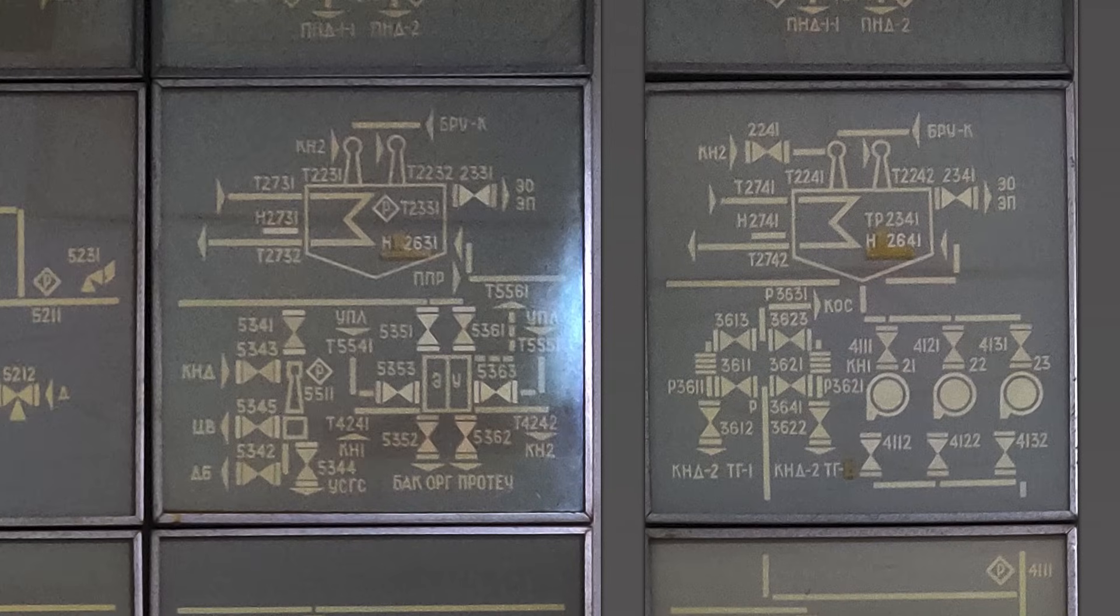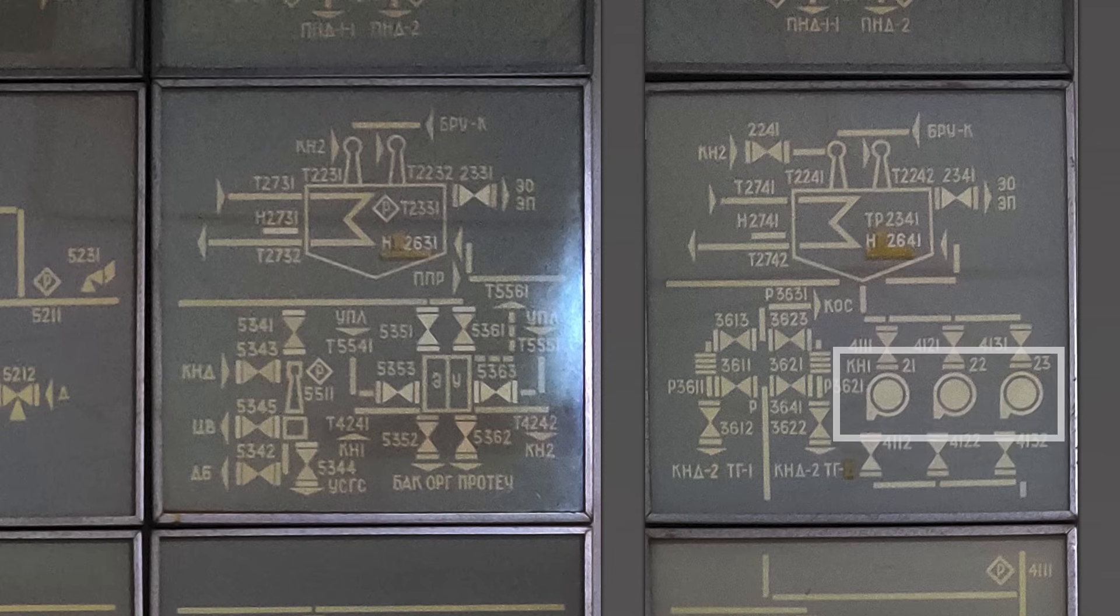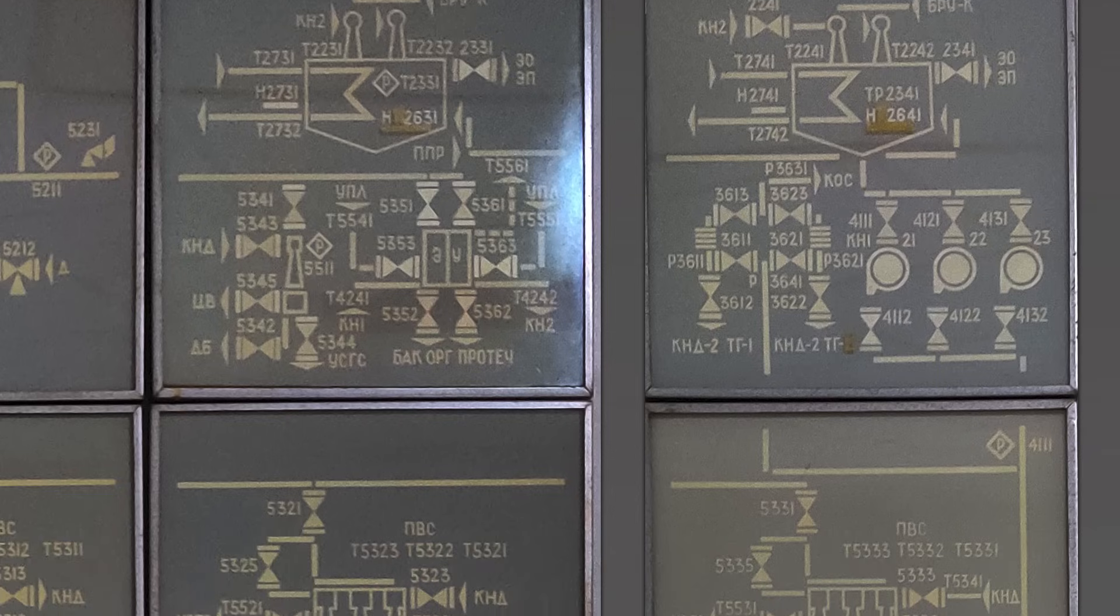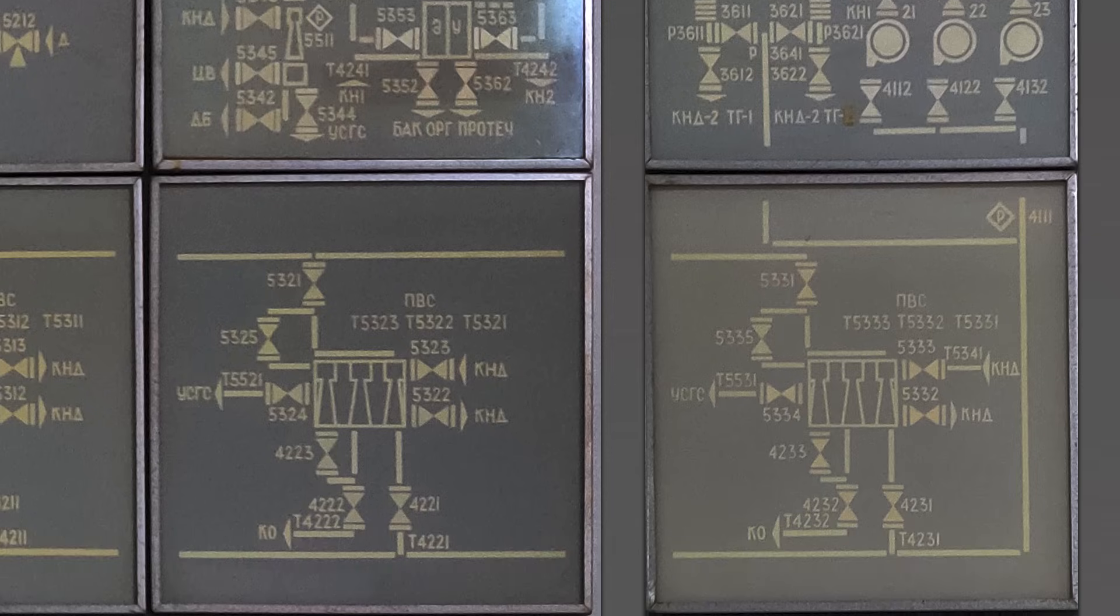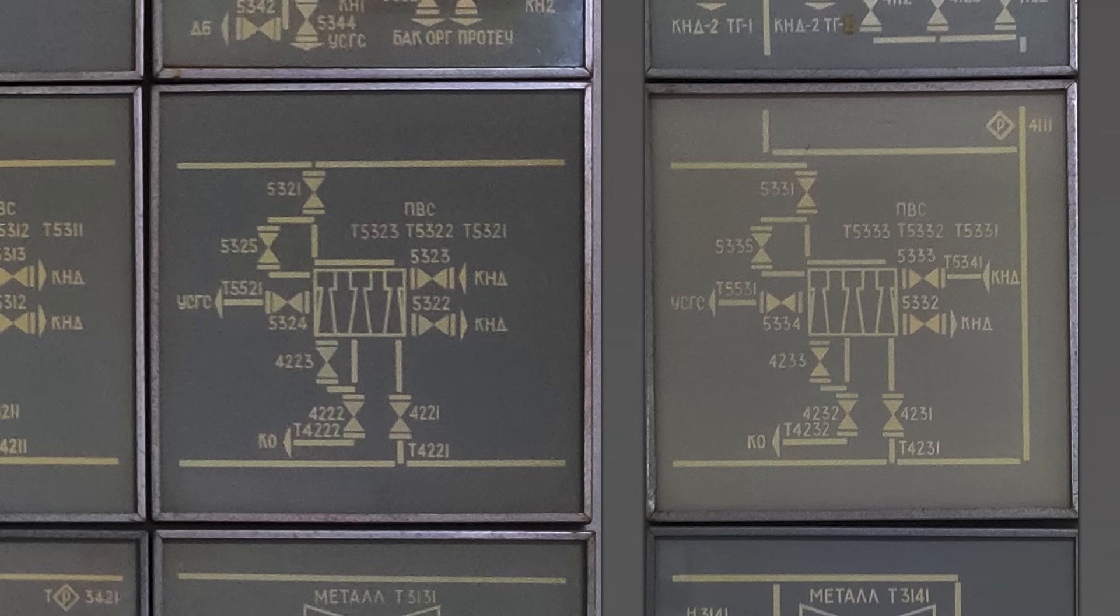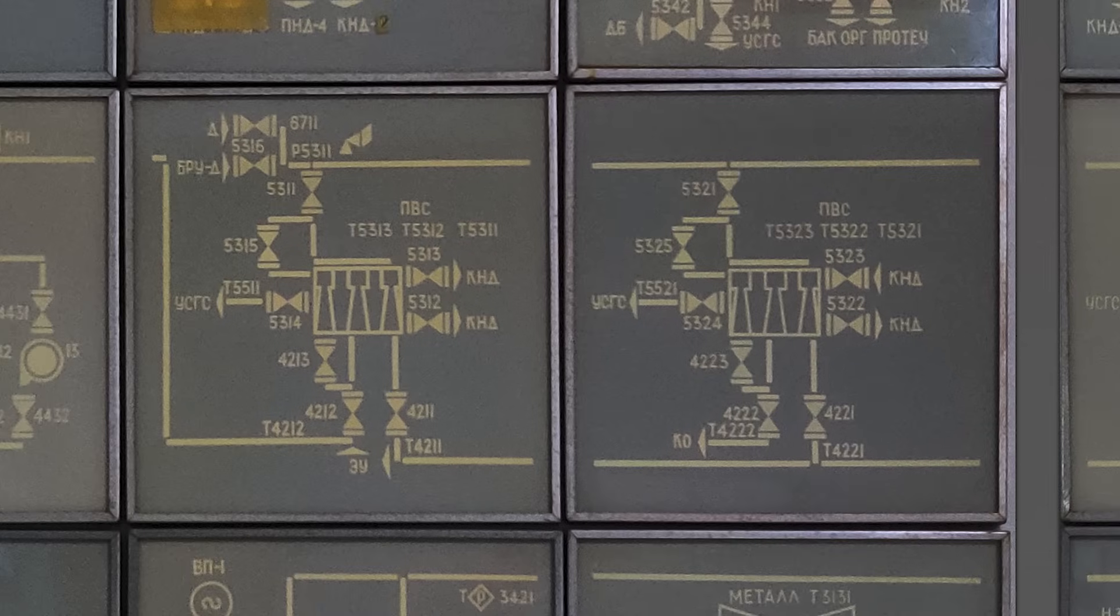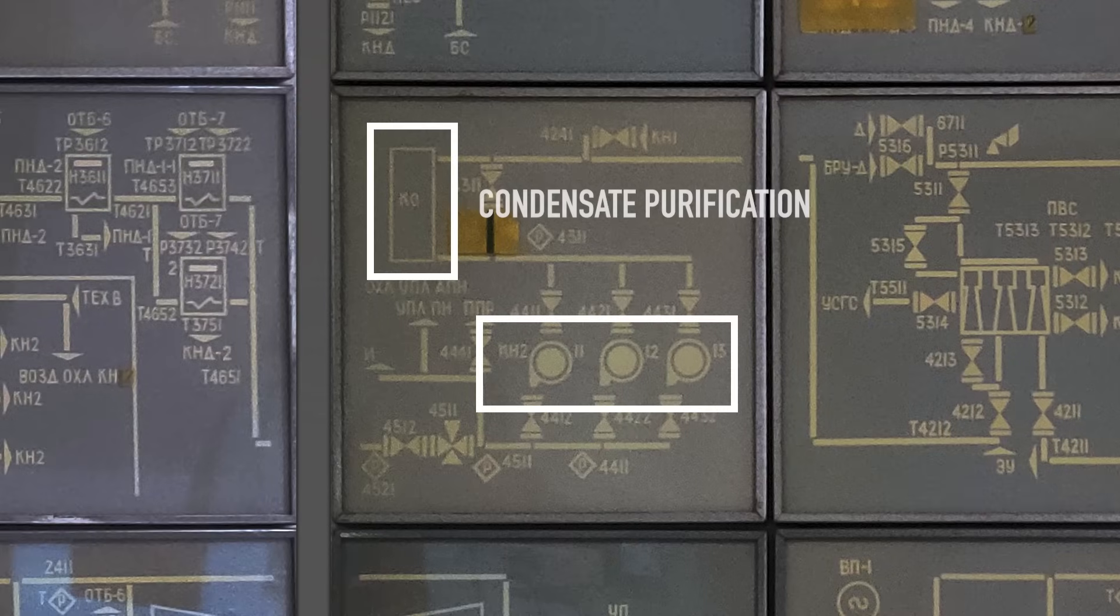You can think of them as tanks with isolated cold water pipes inside, and there the steam condenses into the liquid form. What comes out is now called condensate water. Three condensate pumps move it forward, but still this water is not perfect. It contains gases like oxygen and nitrogen, because again, radiation can split some molecules of water. Plus, there are some noble gases which come from the reactor along the steam. And this is where come these devices called three-stage ejectors. They create a vacuum with steam jets and pull out those gases from the condensate water. And after ejectors, the condensate water is purified and goes through another set of pumps.